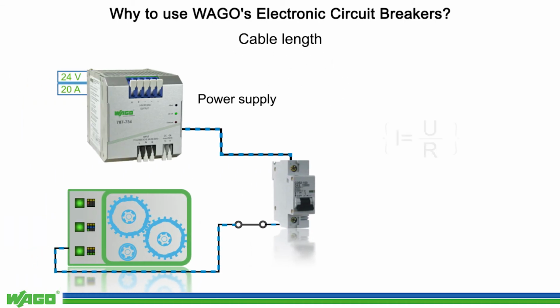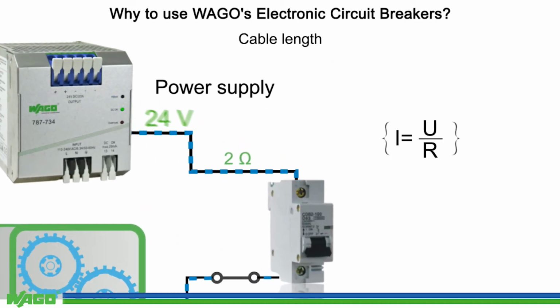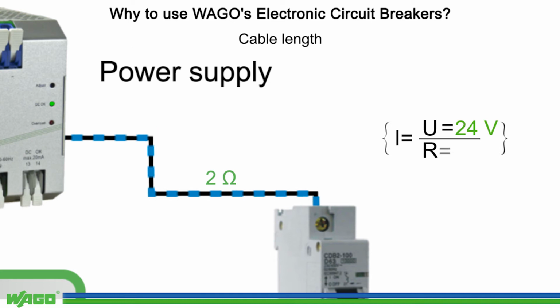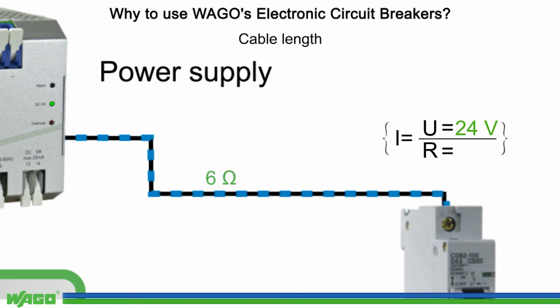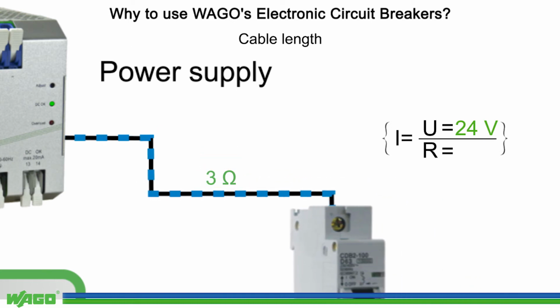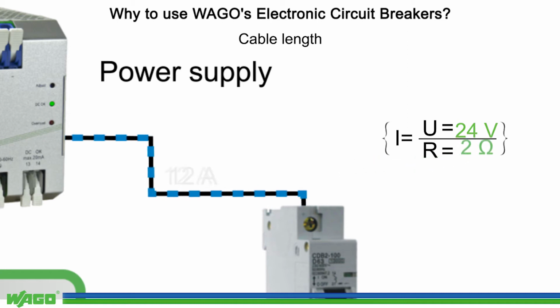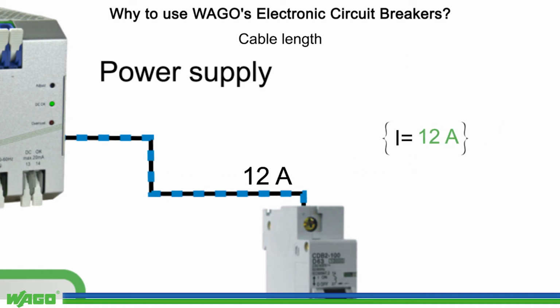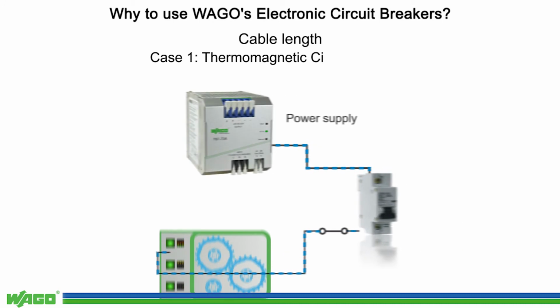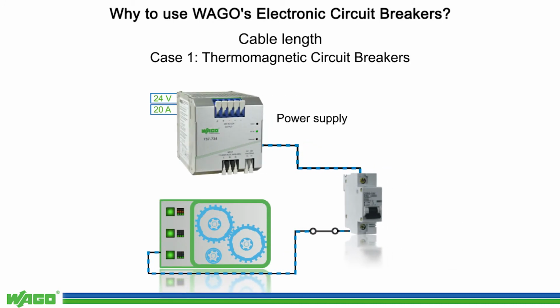Furthermore, the ECBs provide significantly better protection, even with long wire lengths. The cable resistance, which increases proportionally to the wire length, limits the current that can flow in the wire. For example, suppose that the wire resistance in this circuit is 2 ohm. This means that the current cannot exceed 12 ampere in this circuit.